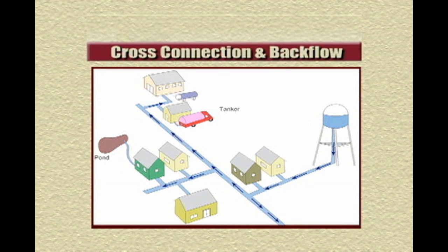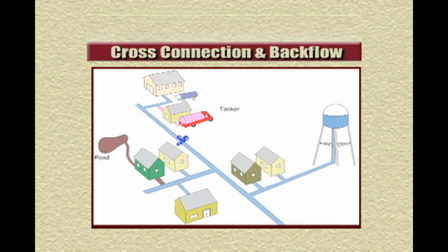Pressurized water systems typically flow from high to low pressure, such as a water main toward a home or a business. During water main breaks, mainline pressure is reduced significantly and may approach atmospheric conditions. When this occurs, water from homes and businesses — or in this case, the tanker and the pond — flows back toward the main.